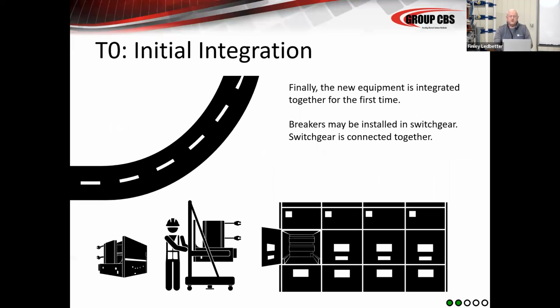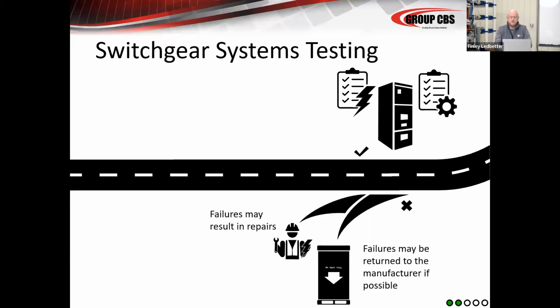At some point, the new equipment is pulled out of the warehouse, or if it's dropped from the truck directly onto the pad and it's assembled together. So the sections are assembled together. There's cross wiring, there's cross busing. The cable has to be connected. The cables have to be tested. The terminations have to be done correctly. The terminations have to be tested. There's a tremendous amount that has to go on, but the switchgear is installed in your plant and the breakers are installed in the switchgear at some point. And there is some testing that goes on with that.